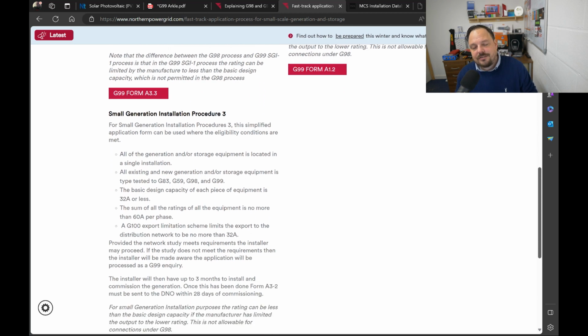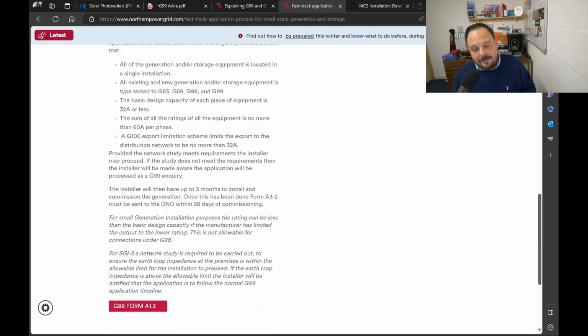Procedure 3 is for the bigger systems, and typically when we're installing Give Energy AIOs, that's what we're using, because usually there's an existing PV array, maybe an addition of new PV, plus the 6 kilowatt inverter in the AIO itself. You need to keep under 60 amps per phase maximum for all the equipment together, and satisfy the G100 export limitation scheme of no more than 32 amps into the network. With the Give Energy system, you can do that and meet those requirements.